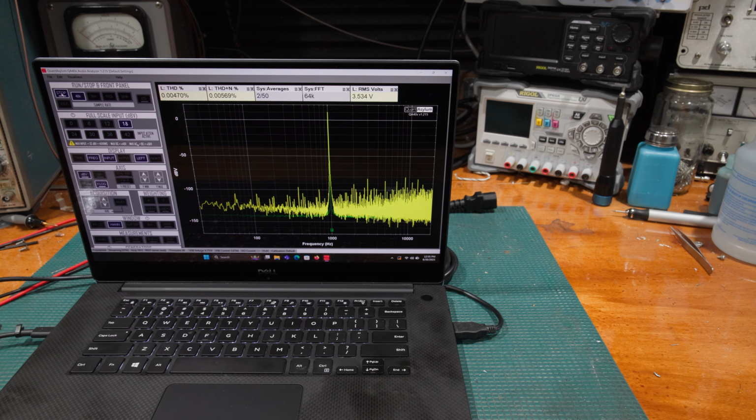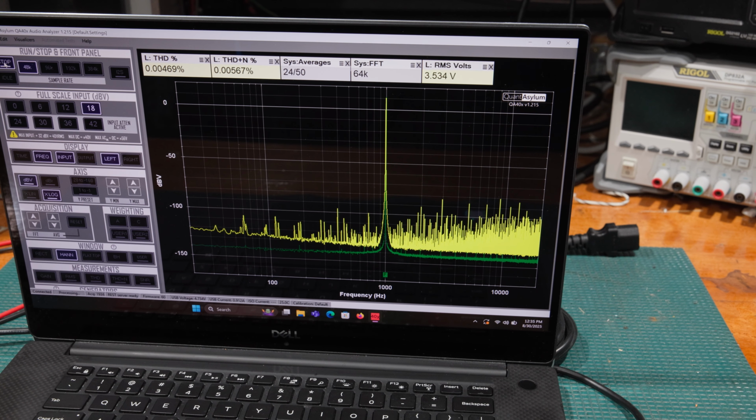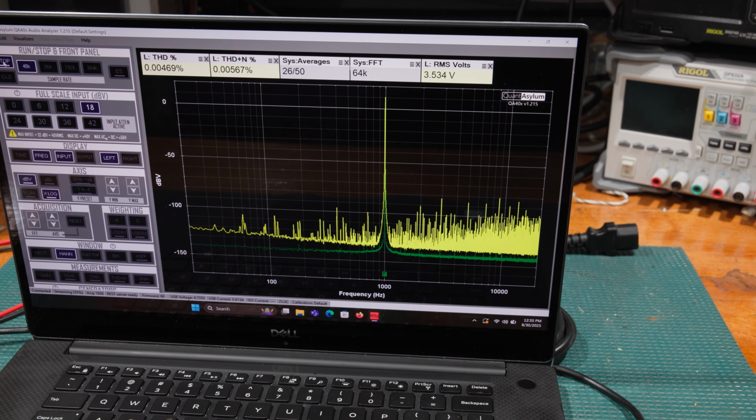All right, moving over to the lab to some of the HP synthesized stuff. We're on the 8904A multifunction synthesizer. Now, I expect this to be slightly more harmonically noisy than a dedicated piece of equipment. Anything dedicated is going to outperform anything multifunction, just by the way the circuitry has to run. With it being synthesized, we should have some of the best stability.